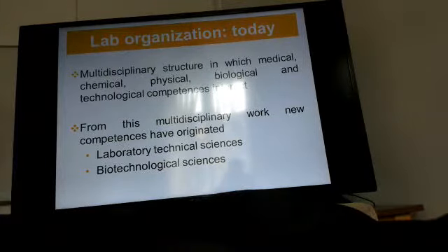So it means that the flow of the lab has to be standardized. We cannot be based on manual operation, because it's not possible that I have one person working with me who takes 2,000 samples every day to evaluate glucose. It's crazy. I have to take a robot. So I have to check the sample, accept it on a web database, verify the ID, verify that the sample is correct, and put the samples on the machine, and the machine has an organized flow that takes all the analytes requested, and at the end I just have to evaluate the results and sign if the results are correct or not.